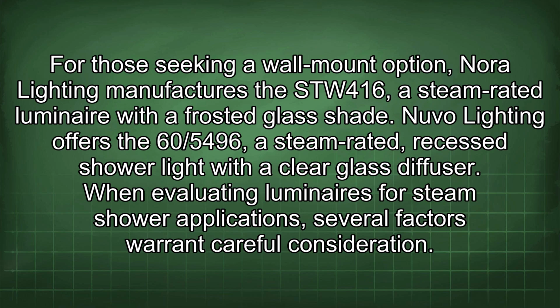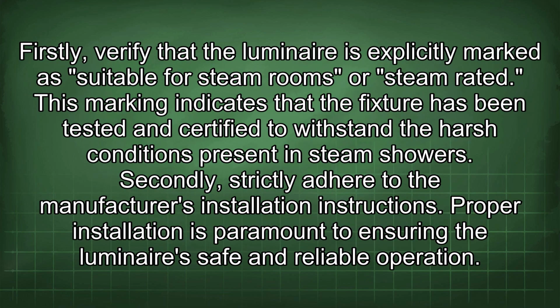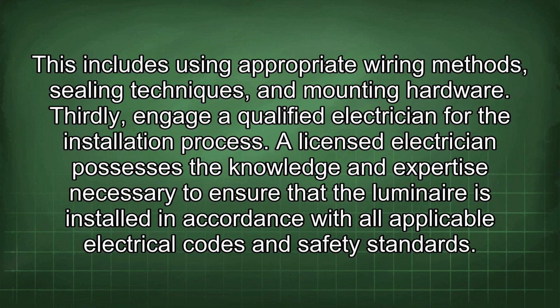When evaluating luminaires for steam shower applications, several factors warrant careful consideration. Firstly, verify that the luminaire is explicitly marked as suitable for steam rooms or steam-rated. This marking indicates that the fixture has been tested and certified to withstand the harsh conditions present in steam showers. Secondly, strictly adhere to the manufacturer's installation instructions. Proper installation is paramount to ensuring the luminaire's safe and reliable operation. This includes using appropriate wiring methods, sealing techniques, and mounting hardware.